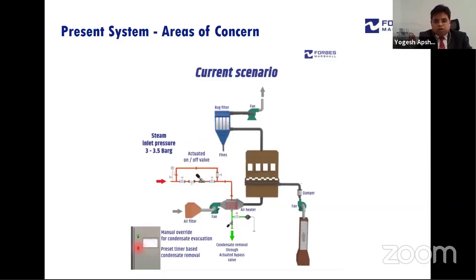And if you see in a typical diagram, this is the air heater battery. This is the steam control with the actuated control valve and steam at 3 to 3.5 bar, and the manual override of the condensate evacuation system, which makes the bypass open so that the steam traps are bypassed. This is the typical scenario in the fluid bed dryer or autocoaters.